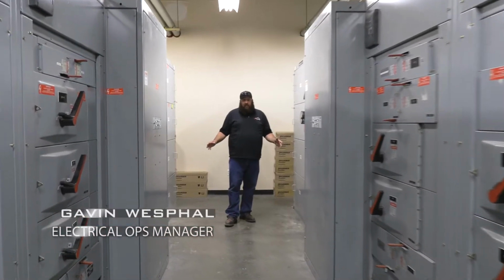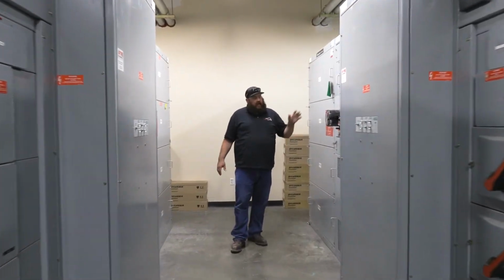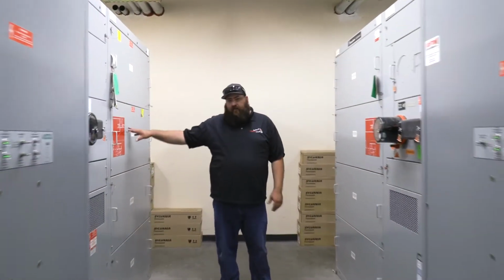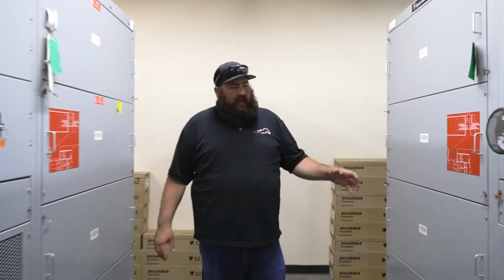So this building runs off of two sections, a 3,000 amp section and a 3,000 amp section. Recently we had them tested. SRP came out, we shut down the whole system, and we had a test company come out and do some basic GFI testing, hi-pot testing. You always need that for city clearance so we can re-energize. And they just make sure they're tripping at the proper time, making sure they're working properly. So when you do have a fault in the system, we know that this breaker is reliable. It's going to shut down, it's going to make sure everything's safe.